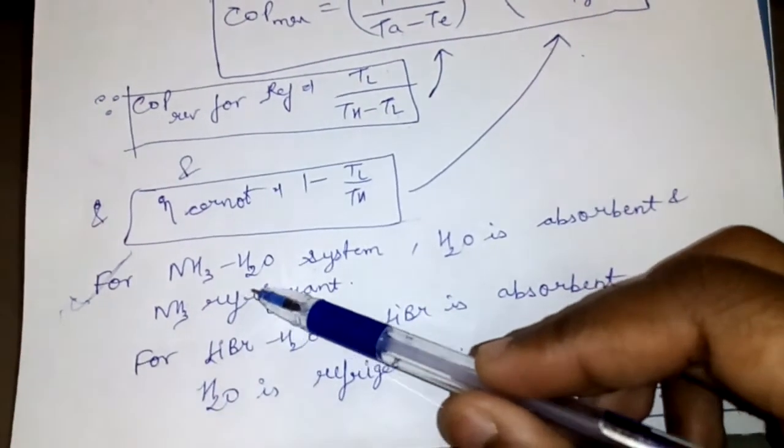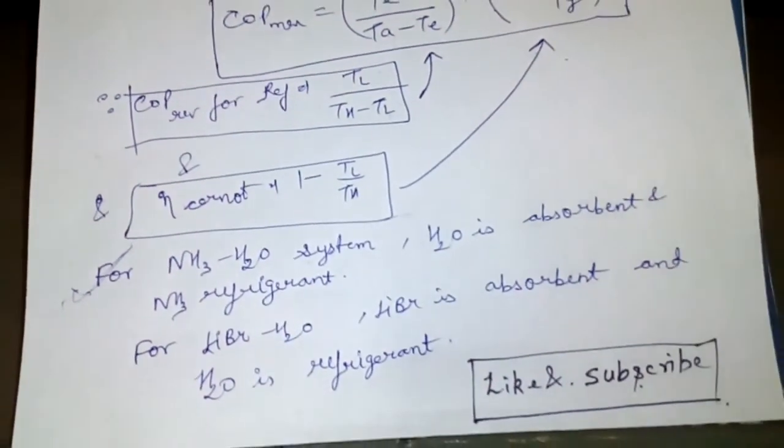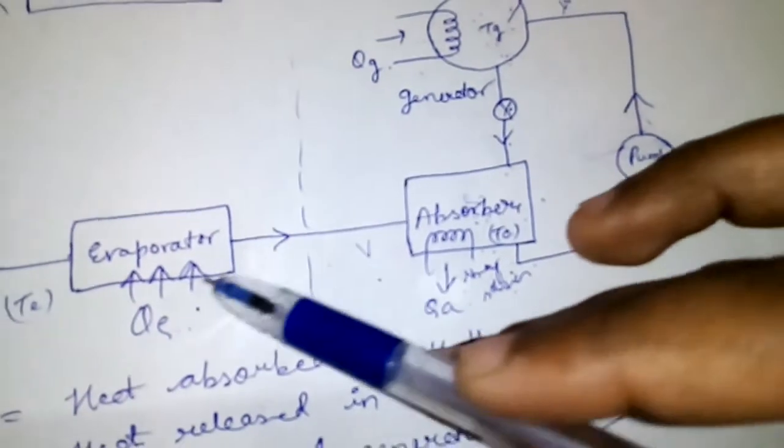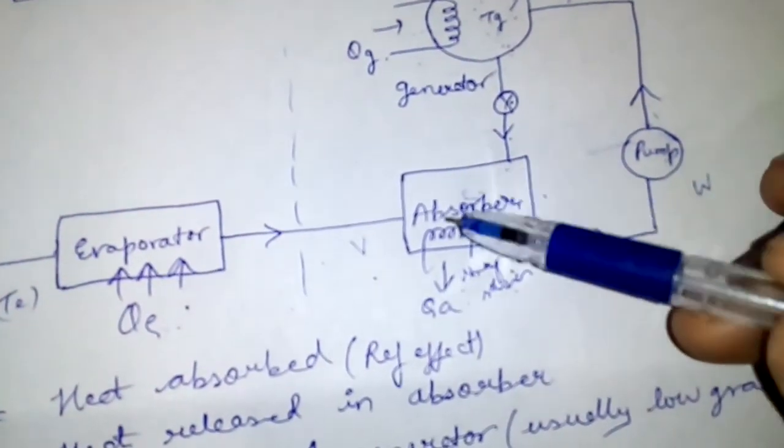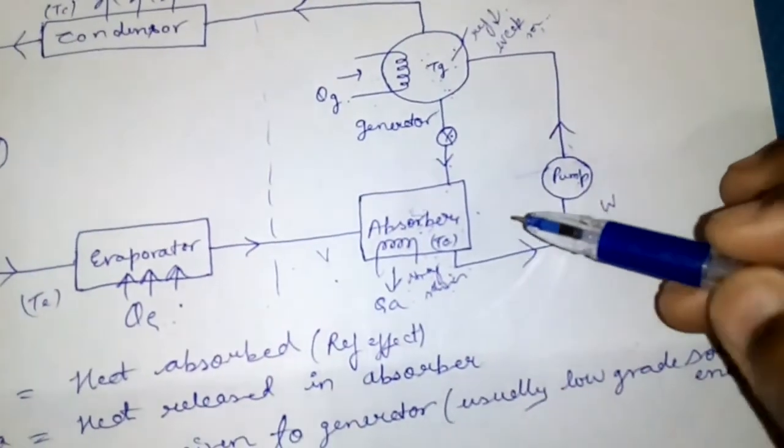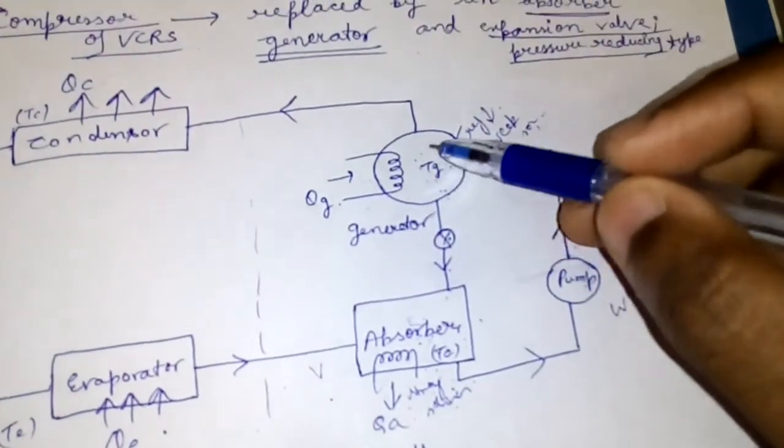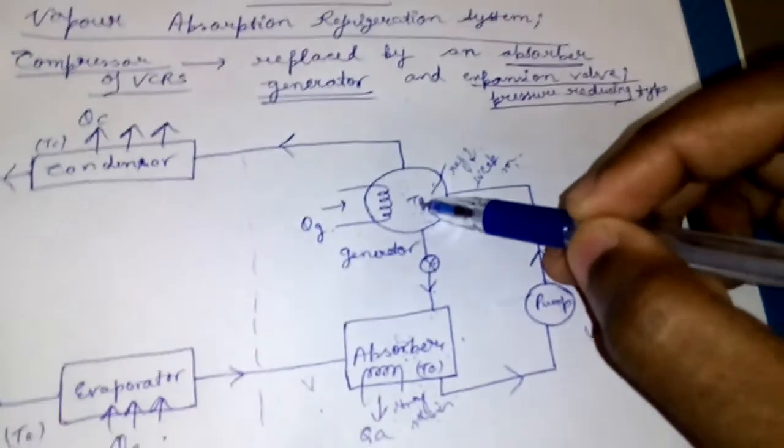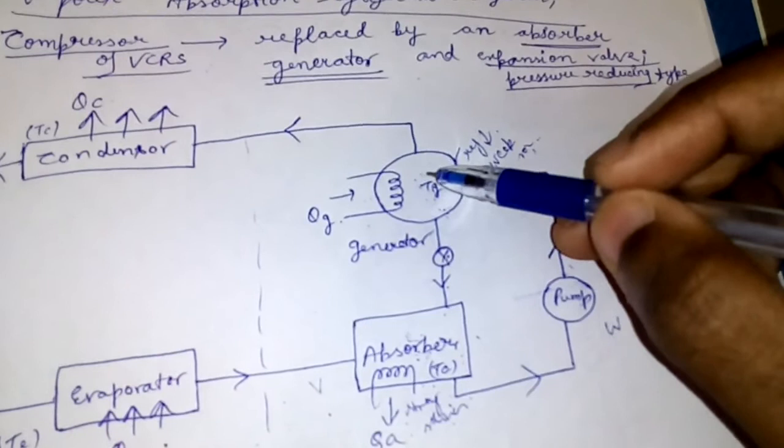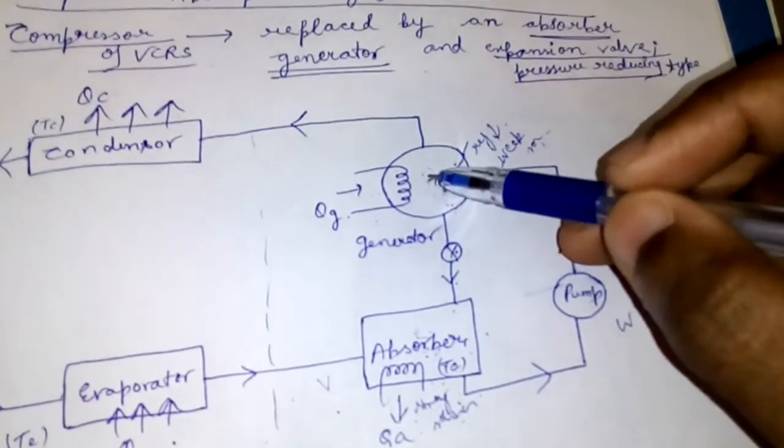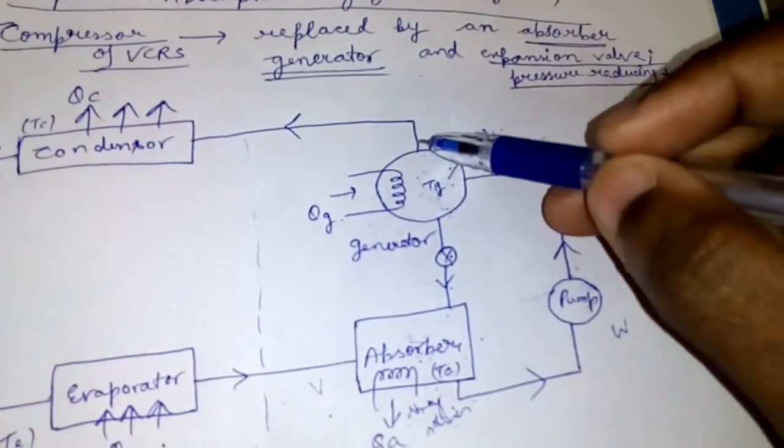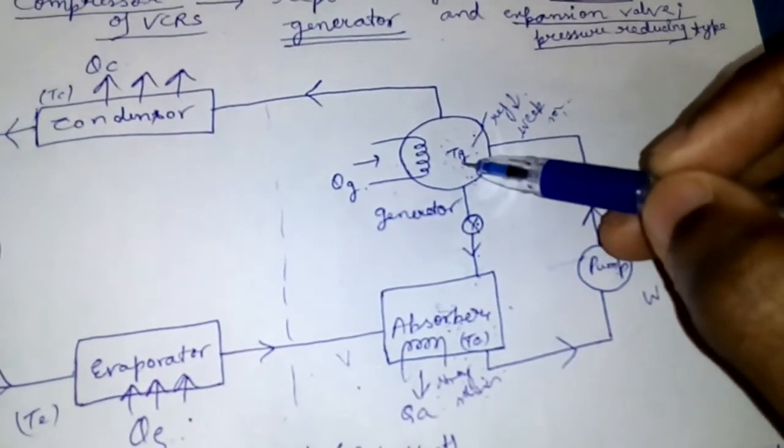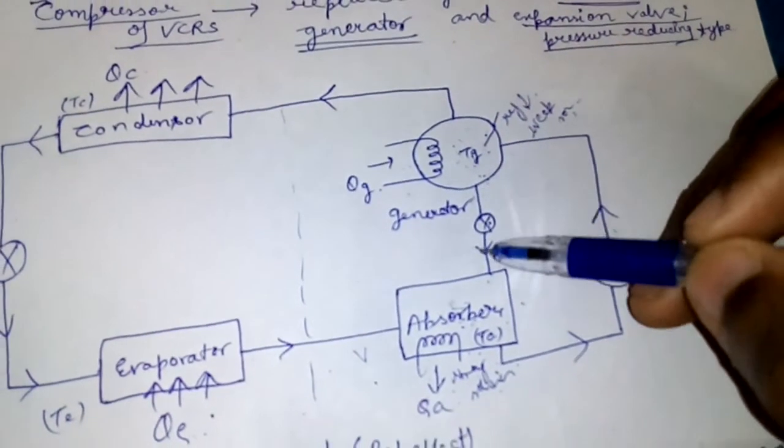It can function very well. NH3 vapors come, they get absorbed here, strong solution is formed. NH3 plus H2O liquid strong solution is pumped here. The affinity at high temperature, because of the heat supplied, the temperature increases, so the affinity of water for ammonia vapors decreases. So ammonia vapors get separated and the refrigerant concentration here decreases, so it is termed as weak solution. It is again brought to absorber pressure by pressure reducing valve.